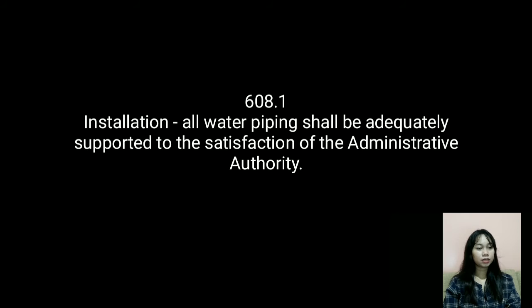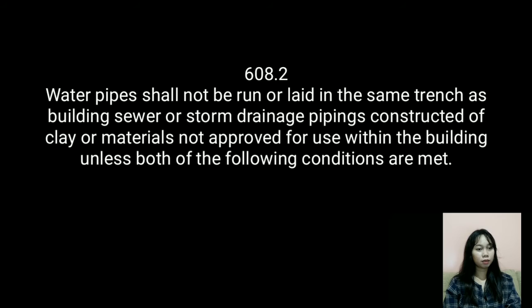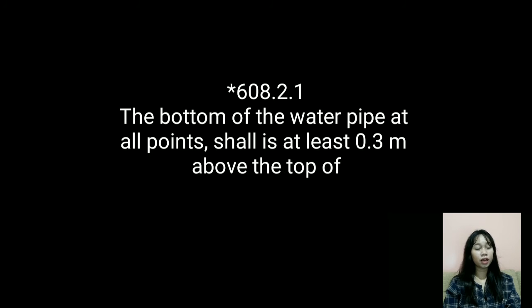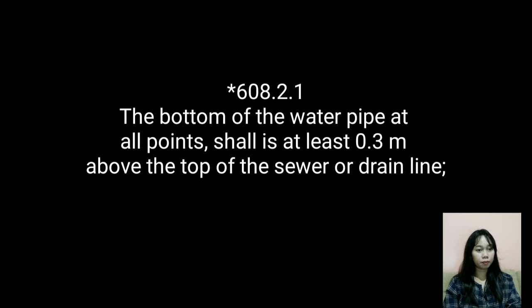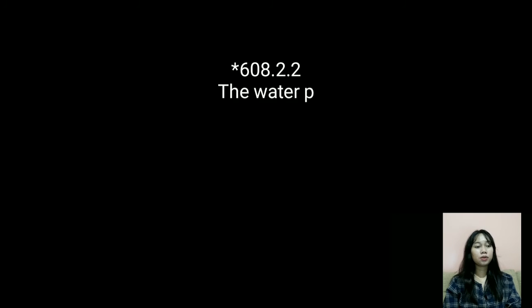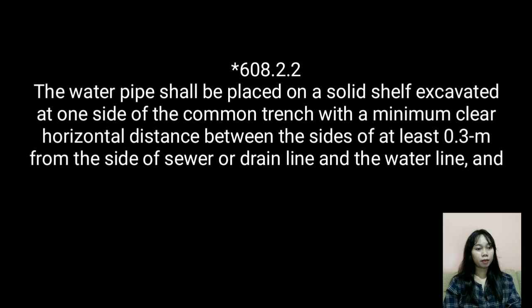All water service yard piping shall be at least 0.3 meter below the finished ground level. Section 608.2: Water pipes shall not be run or laid in the same trench as building sewer or storm drainage piping constructed of clay or materials not approved for use within the buildings, unless both of the following conditions are met. Section 608.2.1: The bottom of the water pipe at all points shall be at least 0.3 meter above the top of the sewer or drain line.